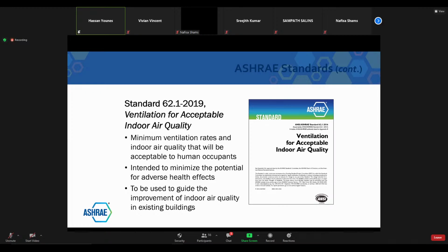There are other requirements like filtration. We know that outside air might have dust, might have some pollutants, so we need to filter it. The recommendation is to go for a minimum efficiency reporting value of 11 on outside air handling units. And now the recommendation from ASHRAE after COVID is maybe to go for 13.